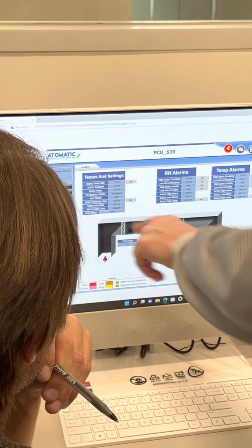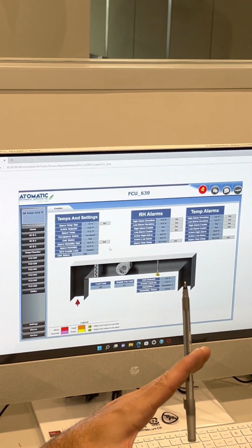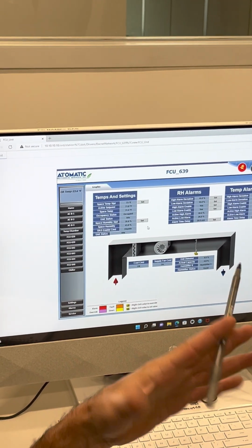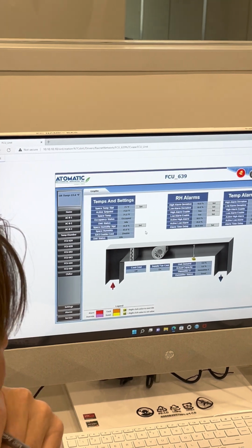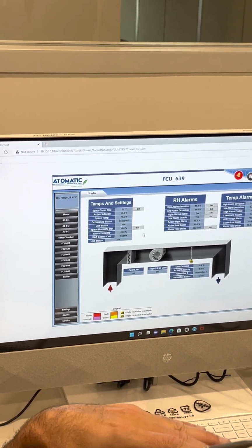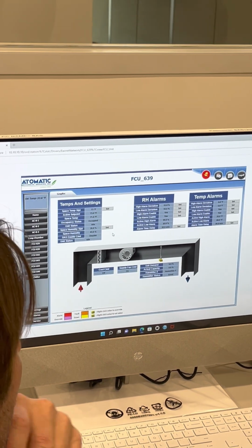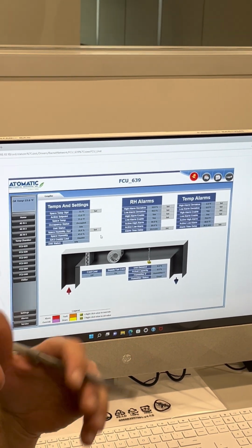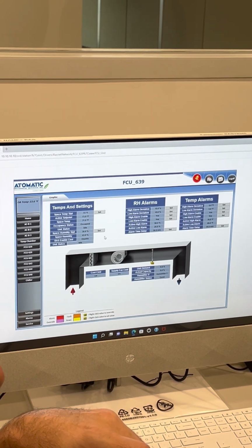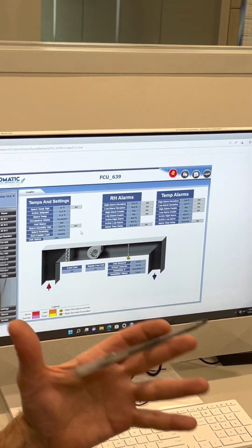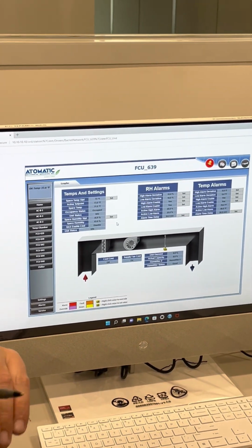Cool. So, space humidity set point is 35. Really? We haven't set that low enough? Well, I did that this morning because we've been having problems. I had it at 40, and we're having problems at 40. No, you're not wrong. I thought they were 40, 45, so I had them all set at 40. But until we get a few things hashed out with the sensors, the way they're reading and stuff like that, that'll help. Absolutely. It'll help tone it down a little bit for us right now.